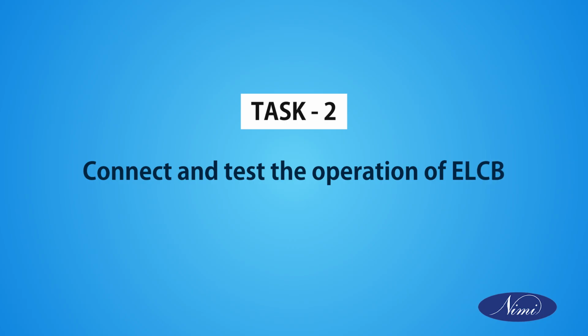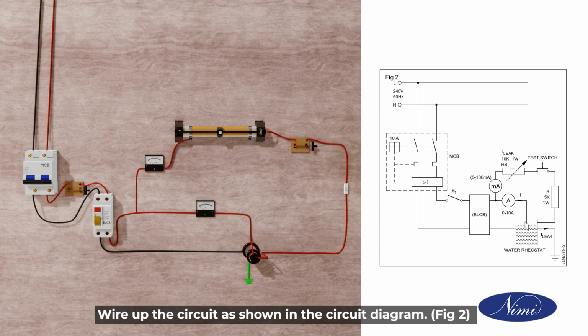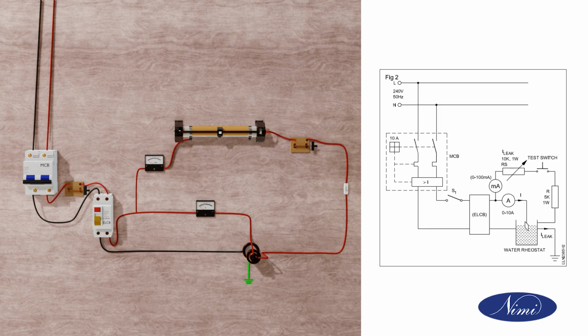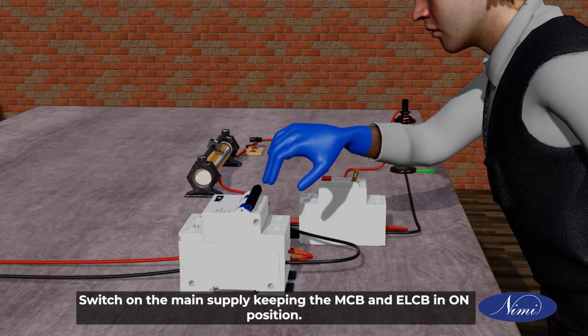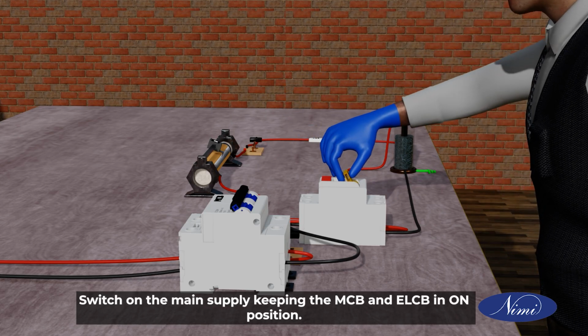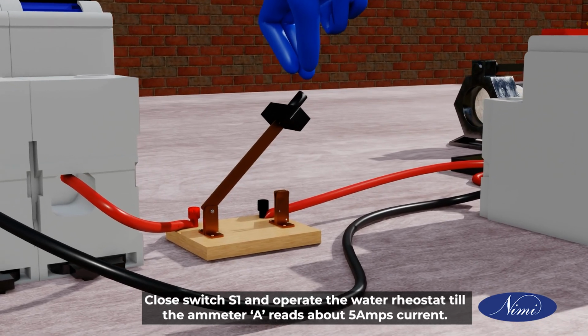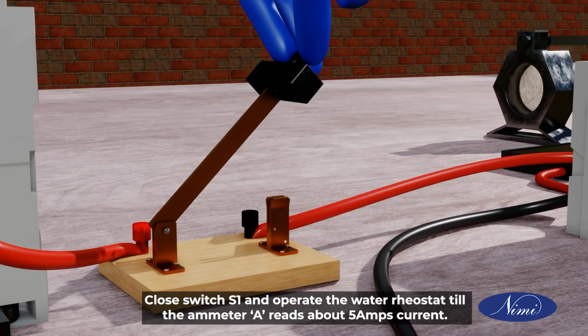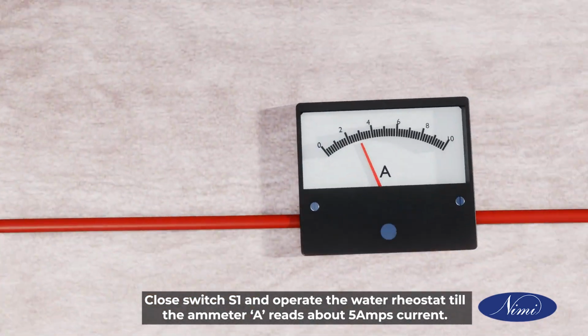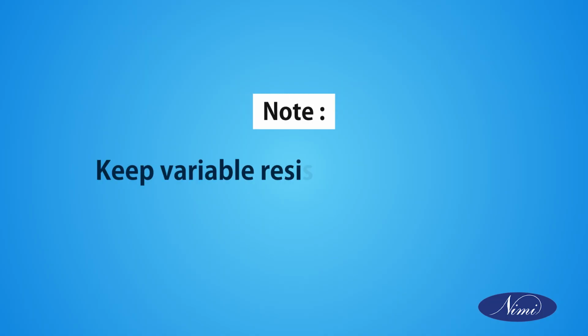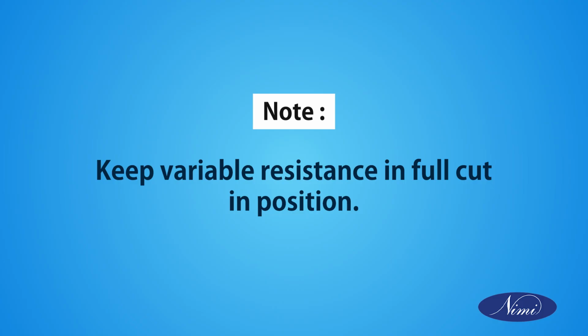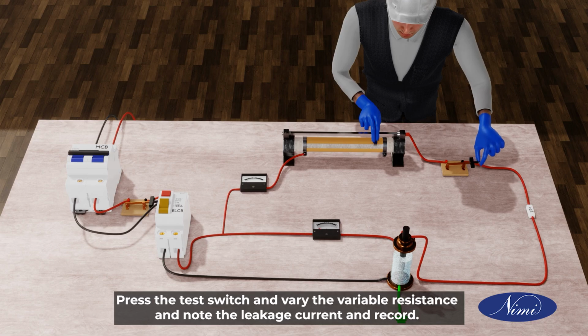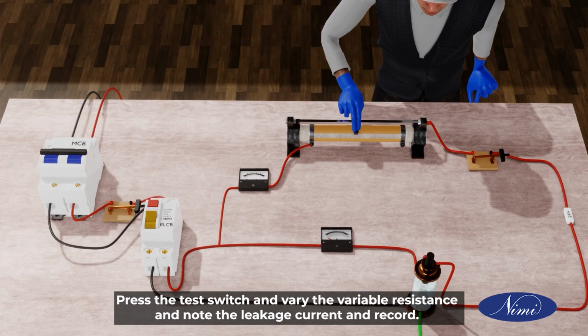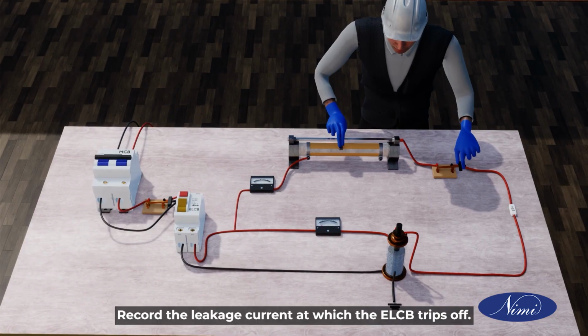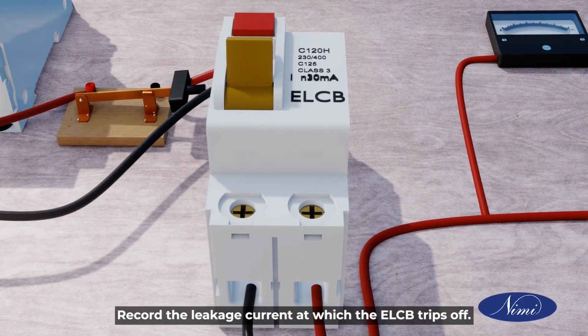Task 2. Connect and test the operation of ELCB. Wire up the circuit as shown in the circuit diagram, Figure 2. Switch on the main supply, keeping the MCB and ELCB in on position. Close switch S1 and operate the water rheostat till the ammeter A reads about 5 amps current. Note: keep variable resistance in full cut in position. Press the test switch and vary the variable resistance and note the leakage current and record. Record the leakage current at which the ELCB trips off.